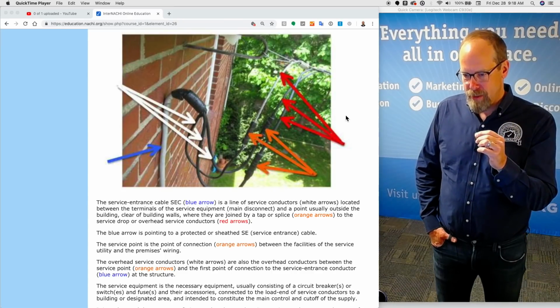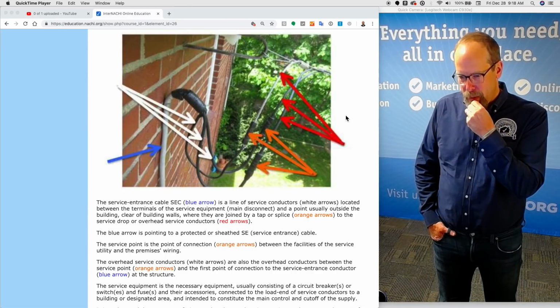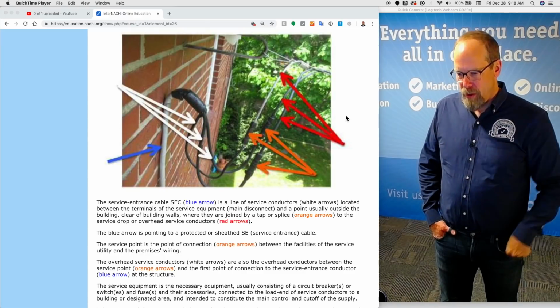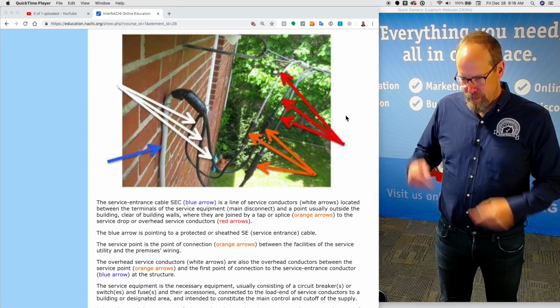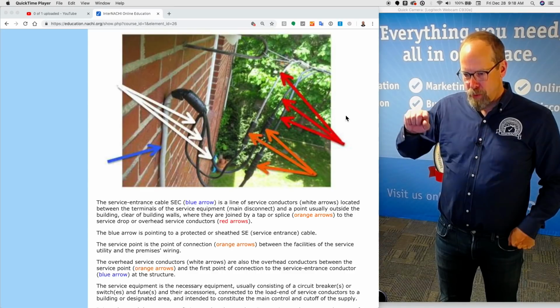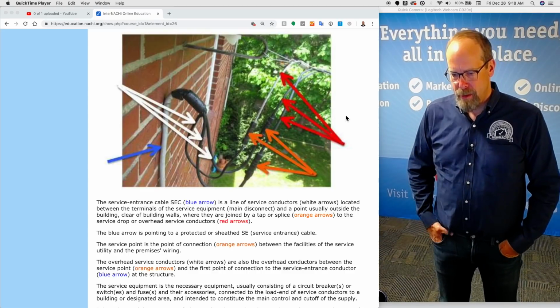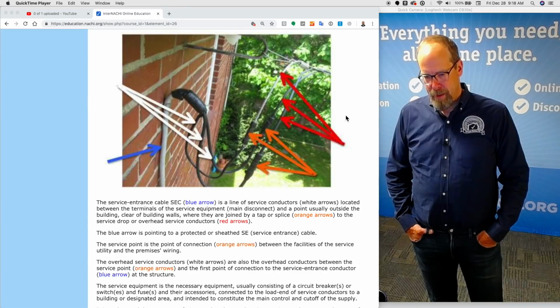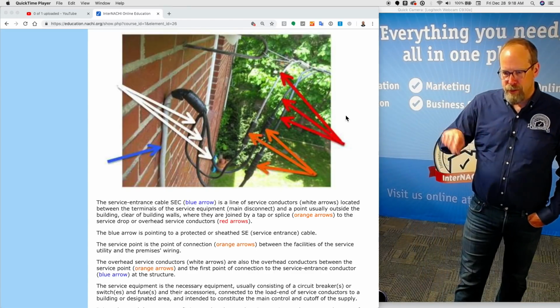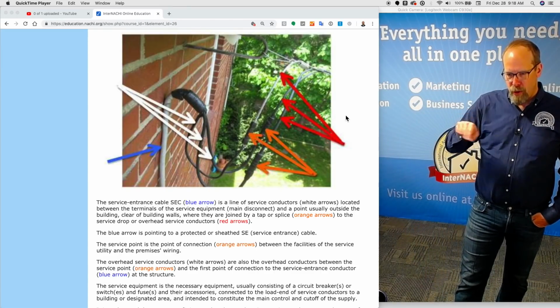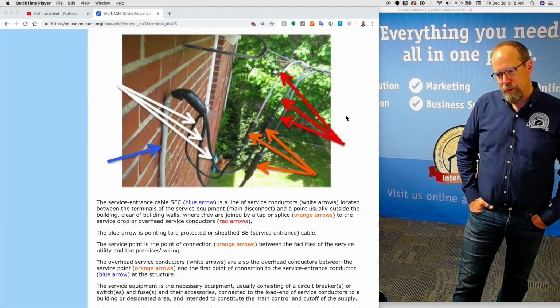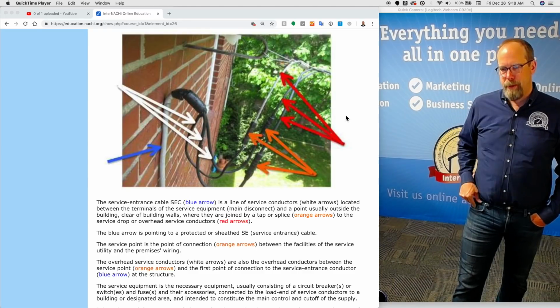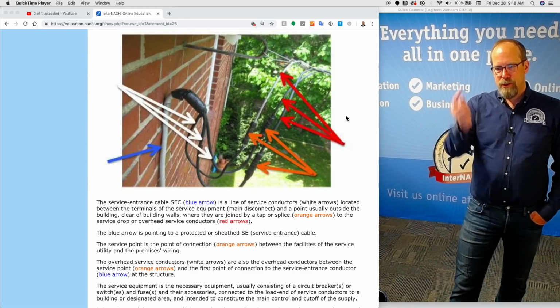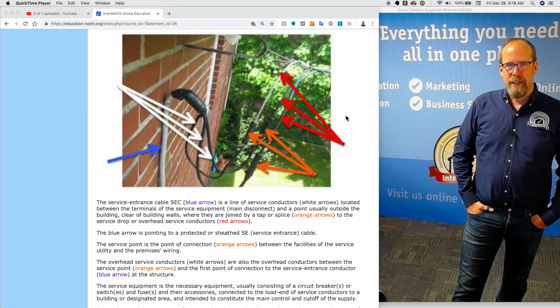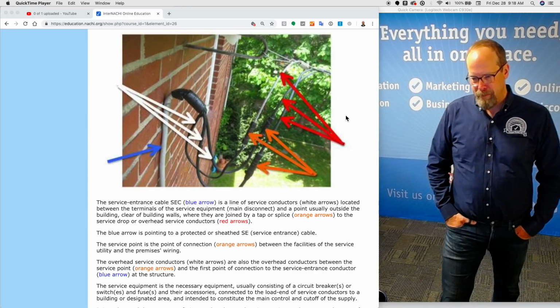The overhead service conductors, those three black wires there, the white arrows are pointing to them, are also the overhead conductors between the service point, splice, orange arrows, and the first point of connection to the service entrance conductor, and that's the blue arrow. So that's the service, the white arrows, the overhead service conductors are also forming the drip loop, and I'll pay attention to that connection as well, or that form. We want that nice drip. So that water, essentially water, doesn't travel down the what? The service entrance cable, SEC, blue arrow.